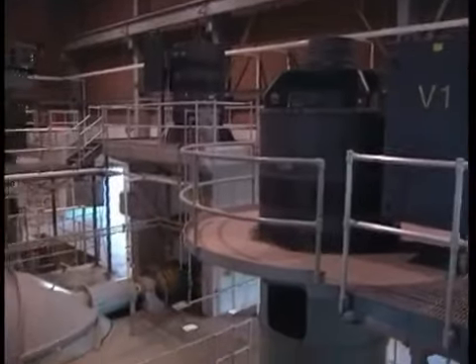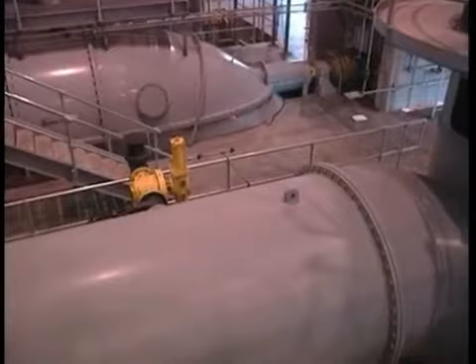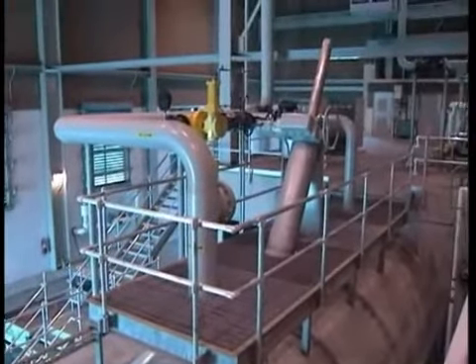These pumps move a lot of water at low head conditions. They're very efficient, easy to operate, and also very easy to maintain because they're high and dry when they're not being used. The drive mechanisms and the pumps themselves are always above water, whereas with vertical pumps, the lower bearings and the impeller would always be submerged in the water, harder to get to. With these pumps, they can be maintained in a dry condition. We have about 28 of them in the system, and we've only taken the cover off of one of them. And the first large ones were put in back in 1912.